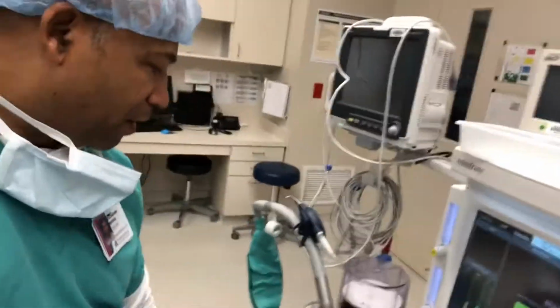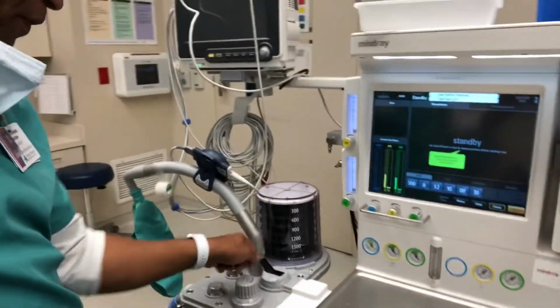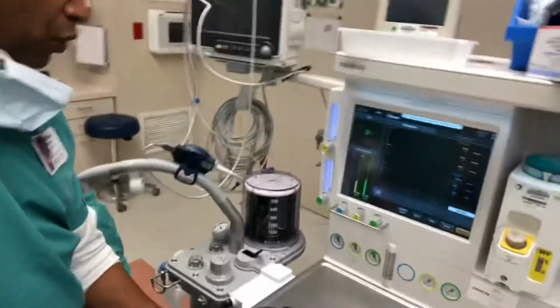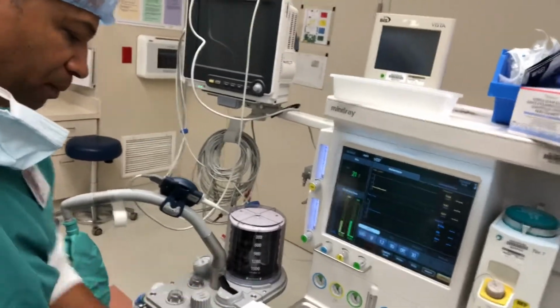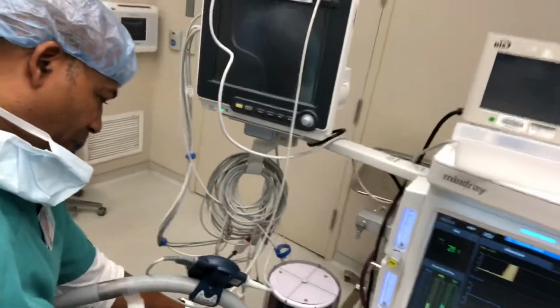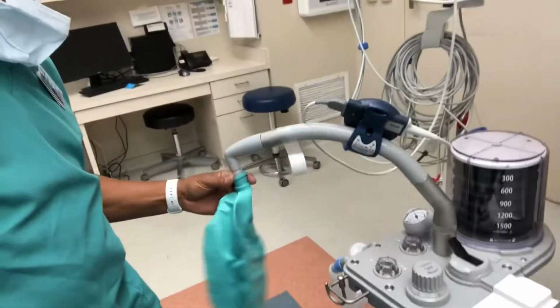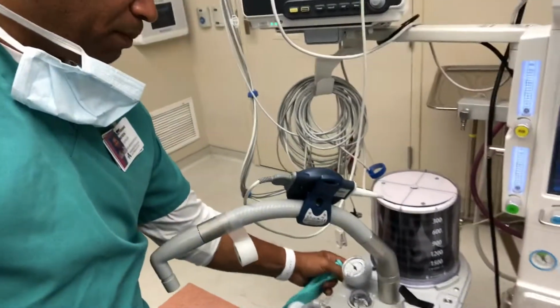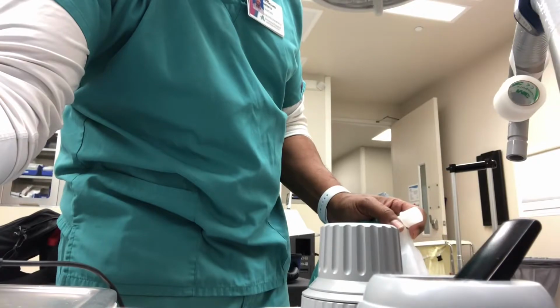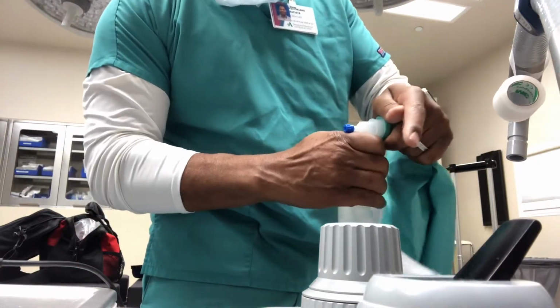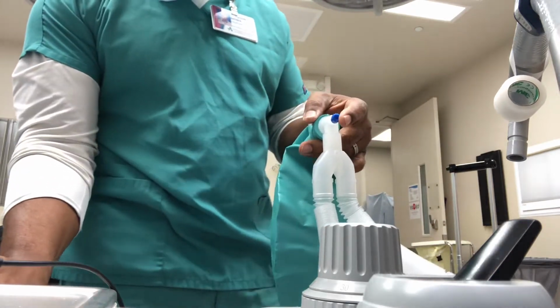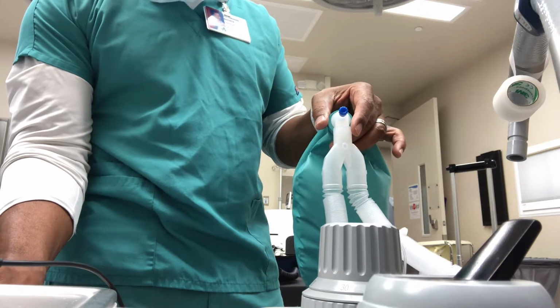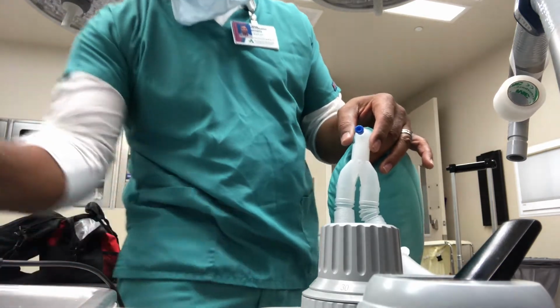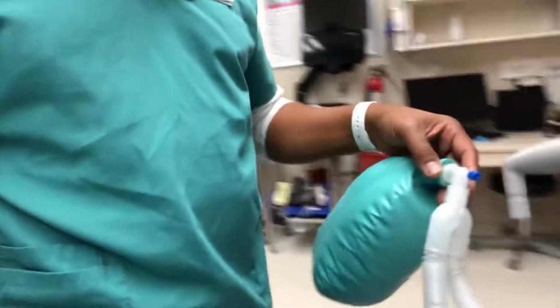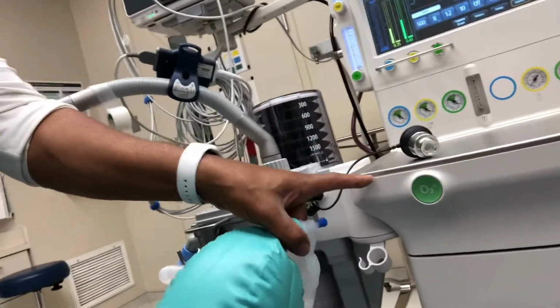So we're going to go ahead and press this little button here as we're going to try to run the unit. Make sure that we have our lung. We're going to move this lung from here, and I'm going to put it on this side of the unit. So I'm going to put this down here just for a minute so that you can see. Then when we press the, I call it the green oxygen button on the front of the machine. It says O2 for those of you that are new. We want to fill up our lung, such as this, after we press this button in here.